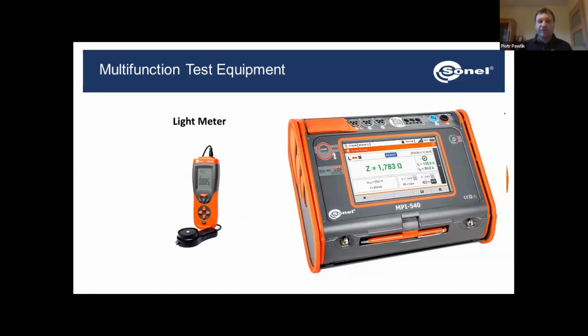Now, in case the multifunction meter is too much for you, you can look at the single function meters, as I was showing you over here. Or in case you are working for power utilities where you need to measure some bigger power objects, like measuring fault loop impedance directly on a transformer or insulation resistance of some medium voltage cable, the multifunction meter will not be powerful enough. For this reason, you may want to look at single function meters, which are just more powerful. They have higher measuring ranges, higher test currents or voltages, and that would be the right solution.